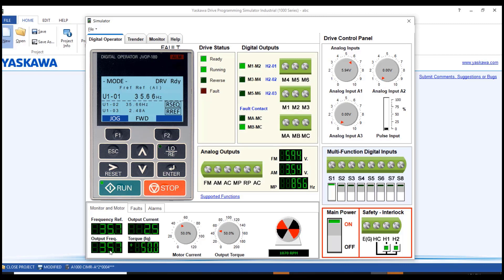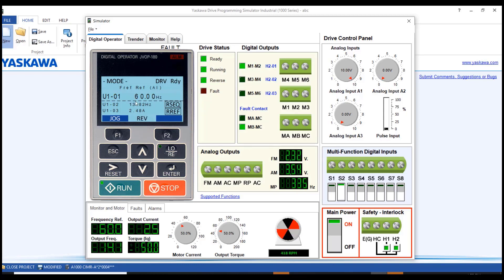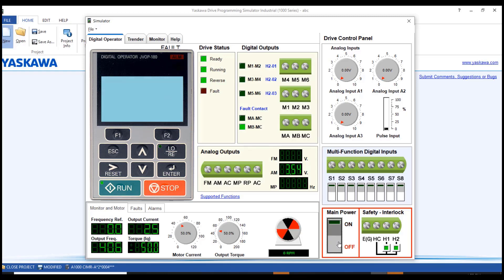Set the analog input back to zero — frequency drops to zero. Turn it off. Now I want to run the motor in reverse. Click the reverse button — S2 is for reverse. Gradually increase the analog input and you will see the motor start running in reverse direction, gradually gaining speed. At max value, frequency increases and the motor ramps up to 60 Hz. The drive status display shows the motor is running in reverse direction.